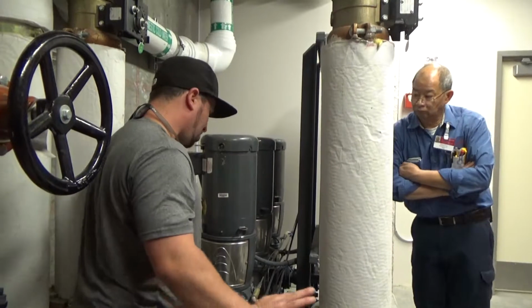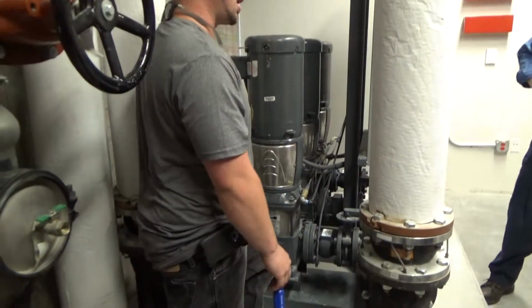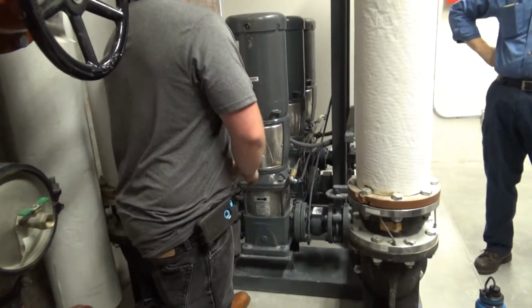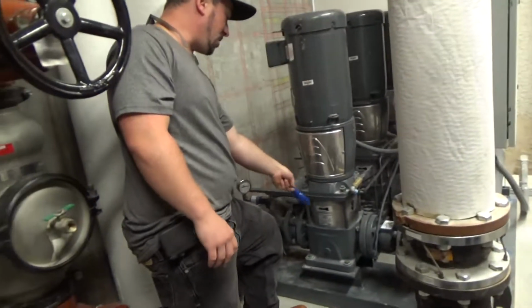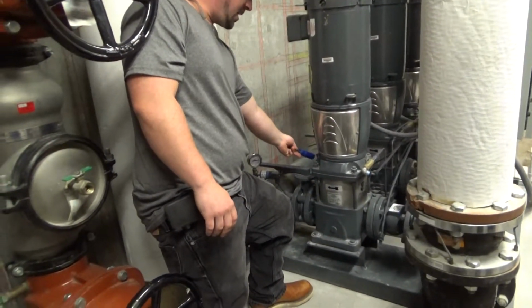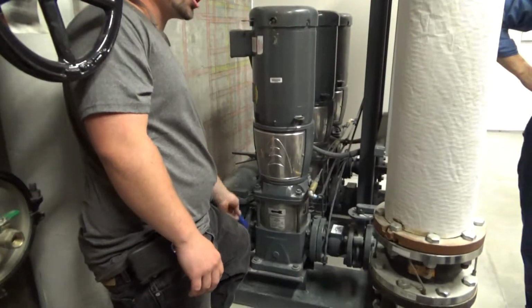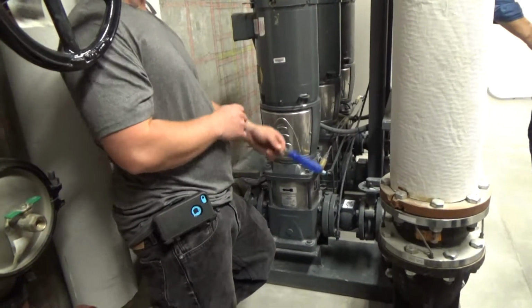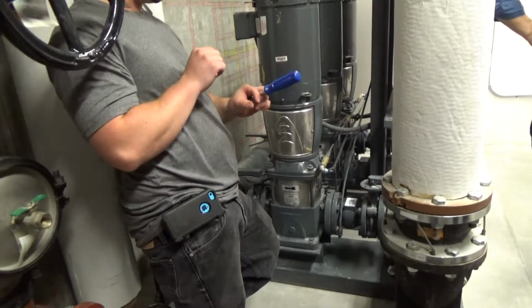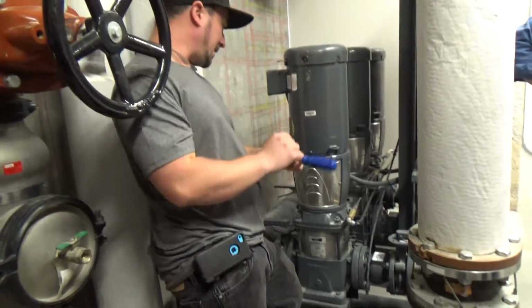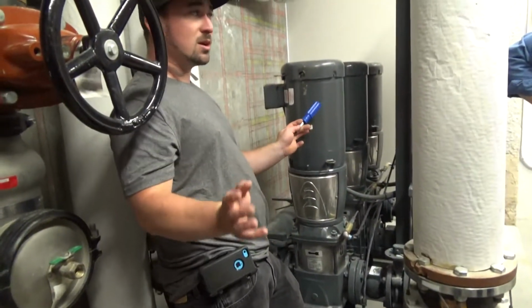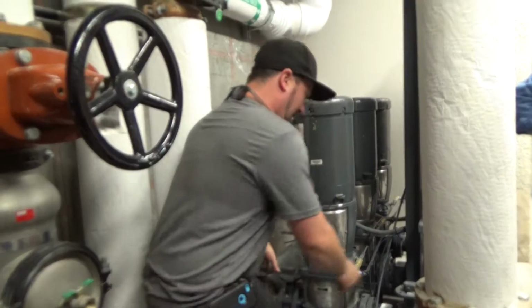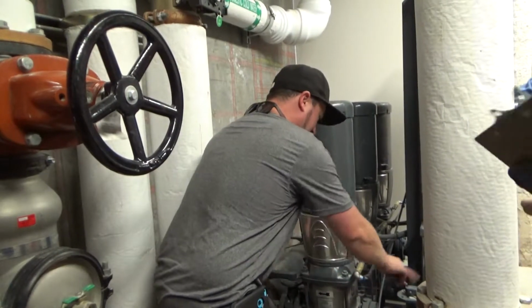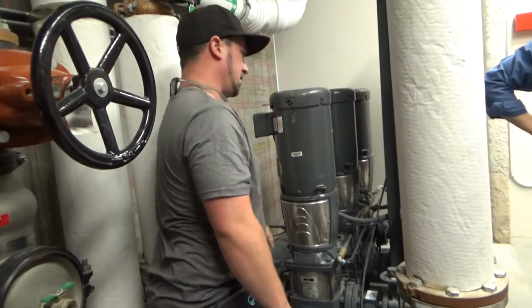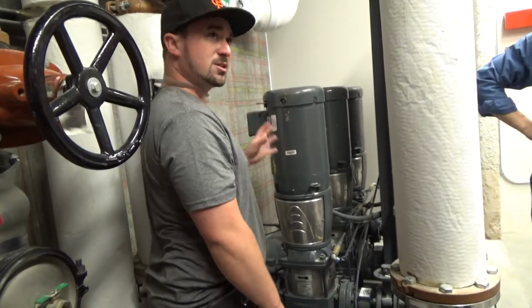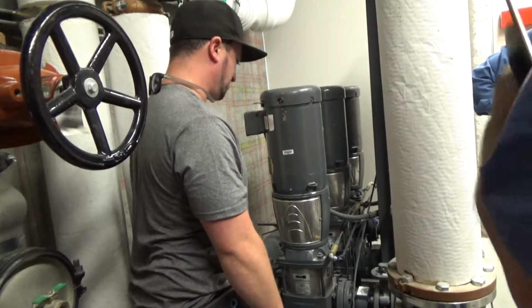The wet end, there's no greasing, there's nothing. It's self-lubricating via the water. One thing also, if you ever do any work, there's an air vent right here on this backside. It's just via compression. So you just loosen the little packing nut on there, get all the air out and tighten it back in. There's no pipe dope or tape or anything needed. So say I do work on this bad boy, put the water back on, I'm going to open that air vent, let it spray out until it's pure water and it's not burping, tighten it back up, and you're good to go.